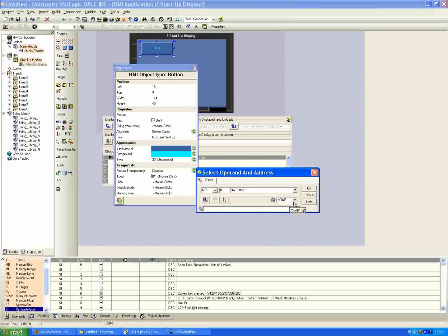Last option you can see here as well is the power-up condition. It's next to this little power-up plug here. The two options for the Boolean value, or the three options I guess really, are none, reset, or set. When you have it on none, it just does not use the power-up condition at all. But what the power-up condition is, when you reset power to the controller, you cycle power, you initialize and reset, any options like that, if you have a power-up condition selected, it will automatically store a reset or a set to this Boolean value. So if we cycle power and we have reset selected, when we turn the controller back on, the state of MB0 will be 0. If we have it on set, when we turn it on and reset the controller, it will be a high state. So with a Boolean, you just really have the on or off selectable.